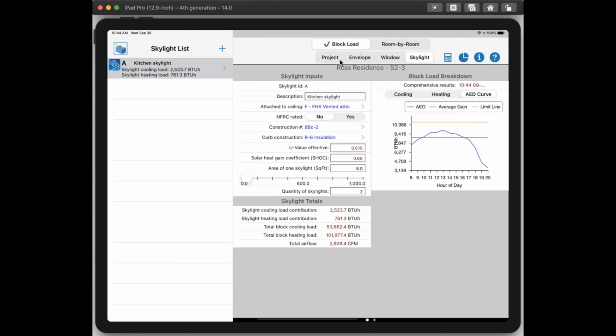So now I could probably get away with a constant volume system in this home because my load is not varying as much as it was before. This AED curve is actually really useful because it shows you a quick load profile of how my load changes. And most of the time it's going to peak in the early afternoon, but there are some instances where, say, most of your windows are facing east. Well, that means it's going to probably peak in the morning, since obviously the sun rises in the east. If most of your windows are in the south or west, it's going to peak more in the afternoon.